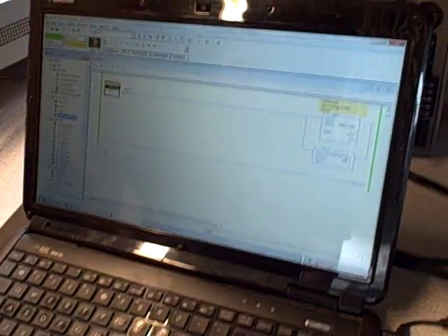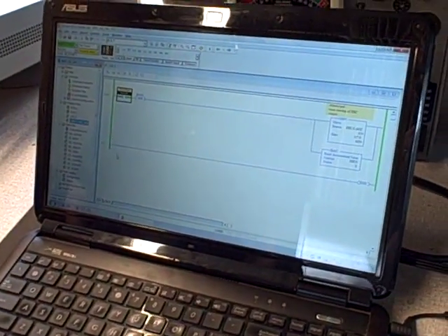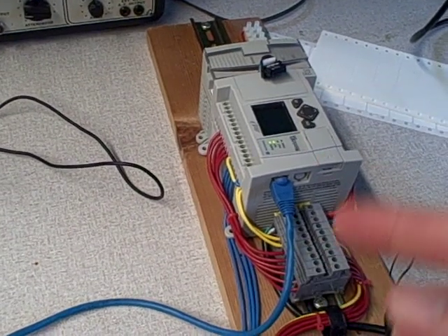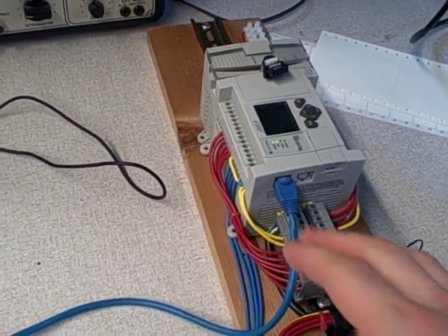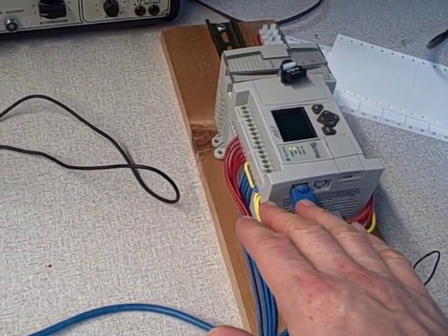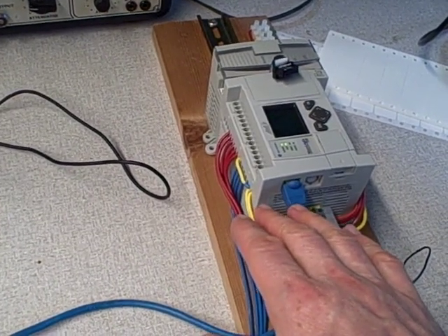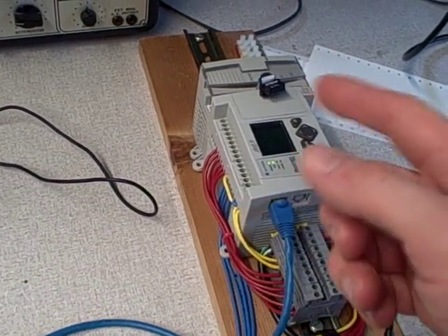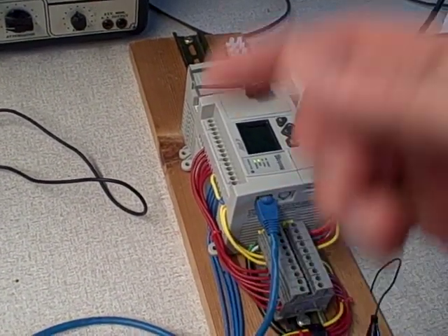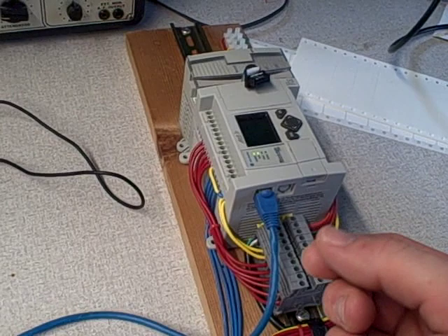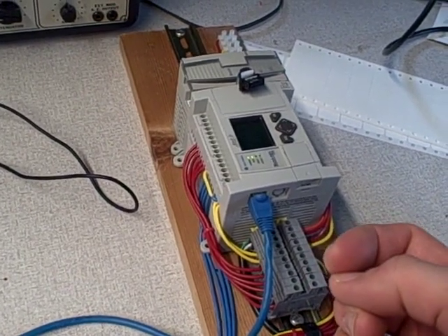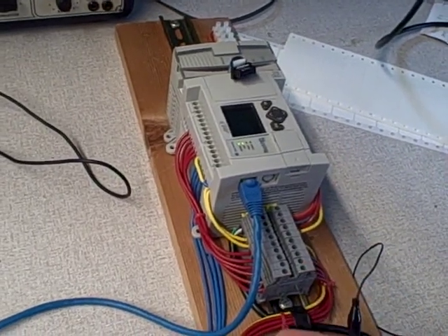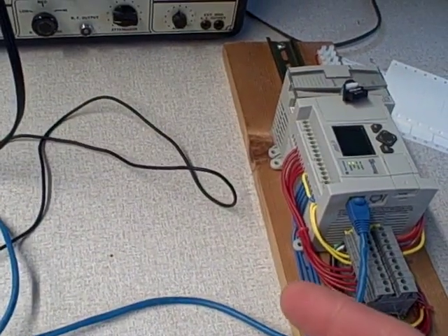So the point of a high-speed counter in any PLC is that we have the ability to count pulse signals that are going faster than the PLC's scan rate. The way this works is that we have a dedicated counter circuit inside the PLC itself that's able to perform counts of events between scans of the program. And then when the program actually scans through, it can see what count value that counter has reached. So that's the notion here. We use this for counting high frequency signals. In the case of the 1100, it's up to 20 kilohertz.